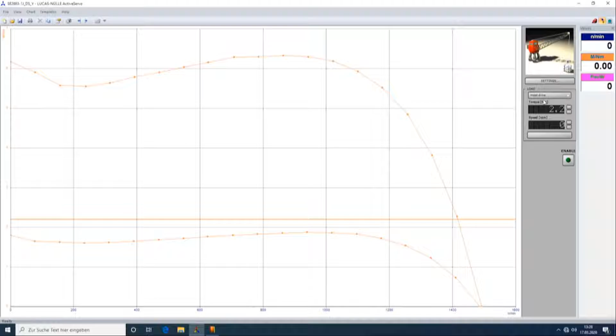Let's try one other example. I will move to another working machine like a hoist drive, which could be a normal tooling machine in the industry. If I look at the motor nameplate, I see, okay, this motor has a value of approximately 0.37 kilowatt, so the torque should be around 2 and something Newton meters. So I apply a value of 2.2 Newton meter for the torque. And now I try to run the motor with the star-delta switch.